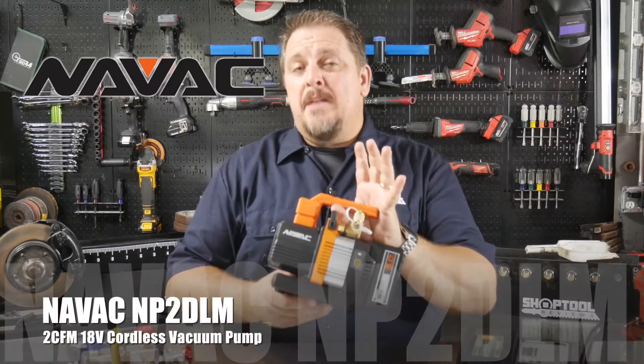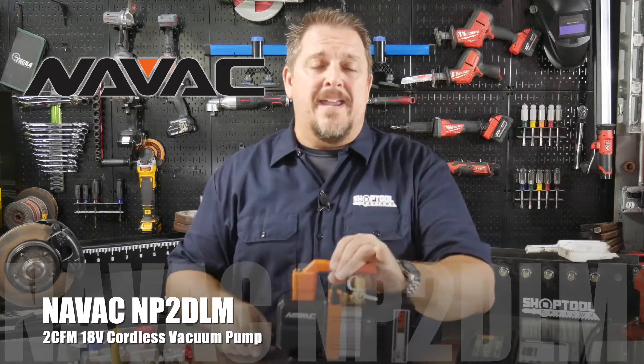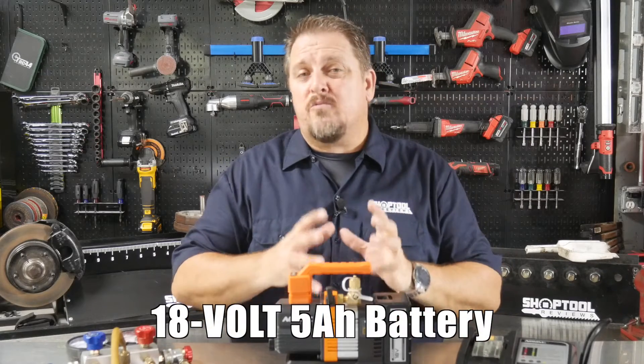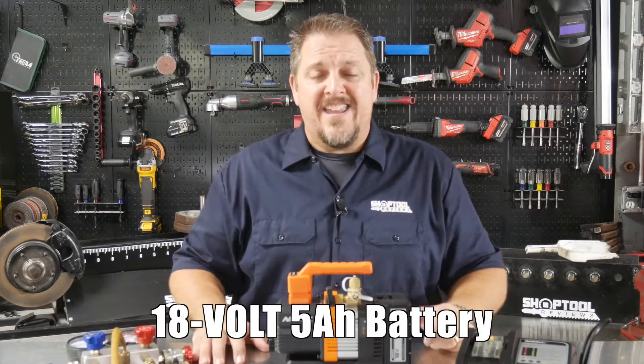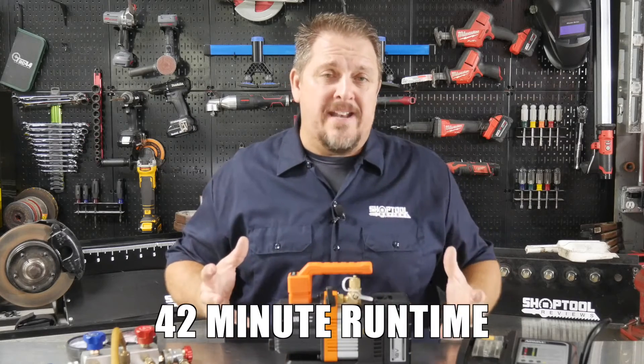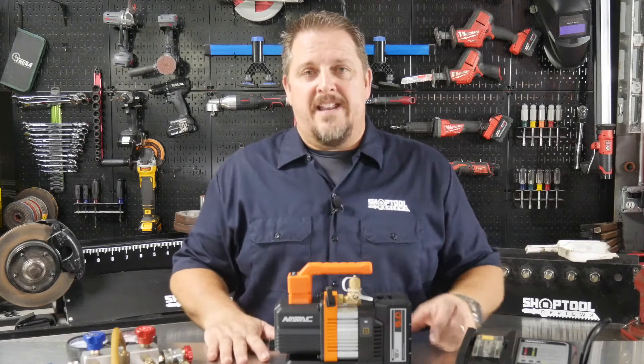This is the Navac NP2DLM and it is their cordless 2 CFM vacuum pump. It runs off their 18 volt 5 amp hour battery and will run this unit for about 45 minutes. We actually did a shop run time test and got 42 minutes out of it, so we validate that 45 minutes.